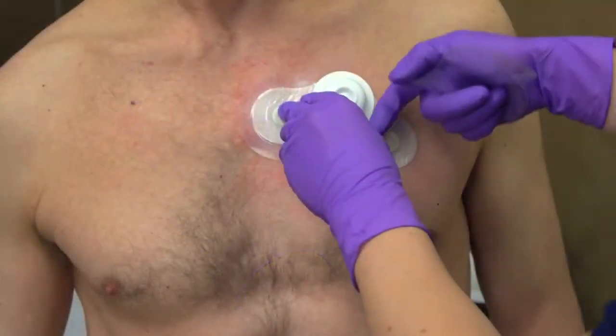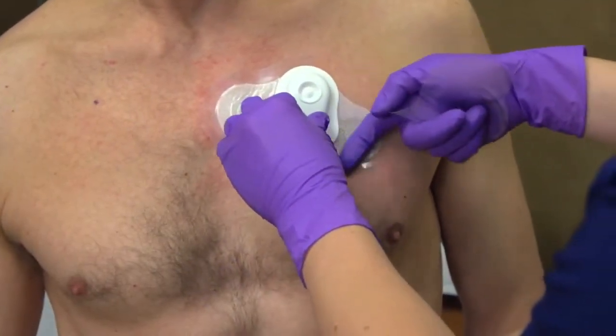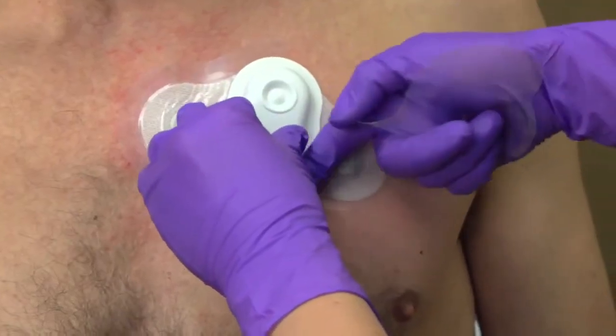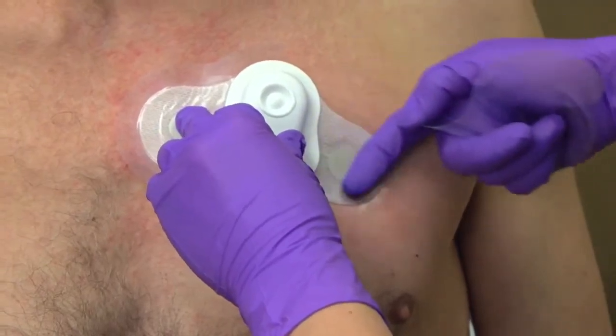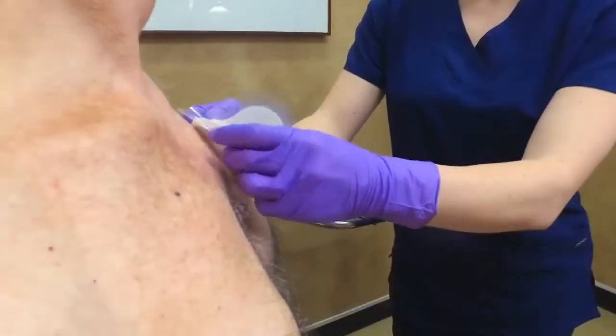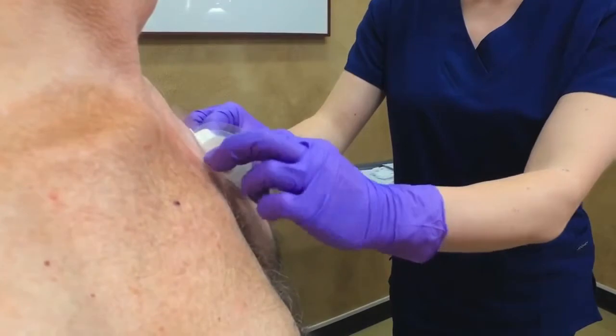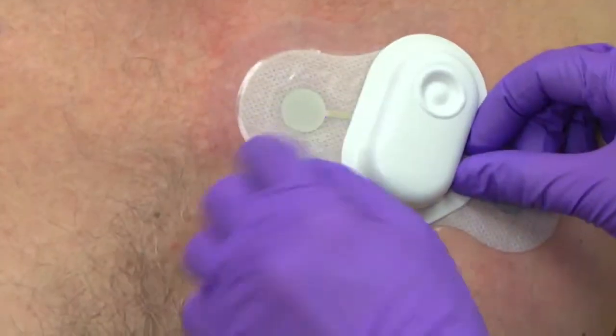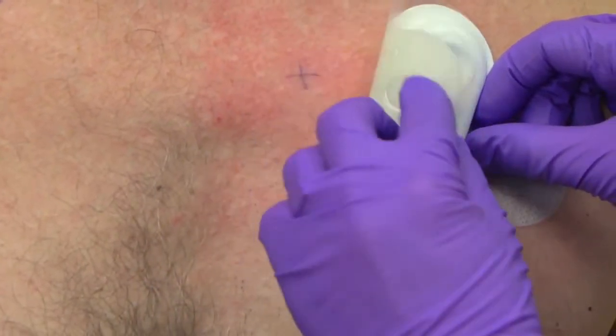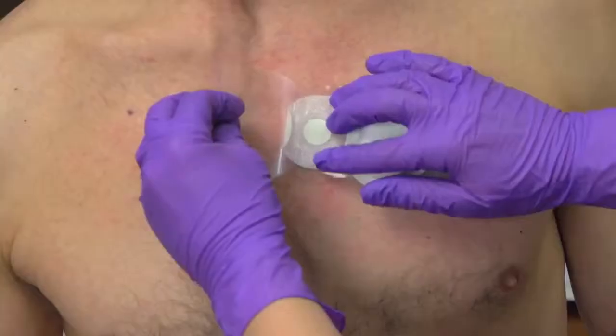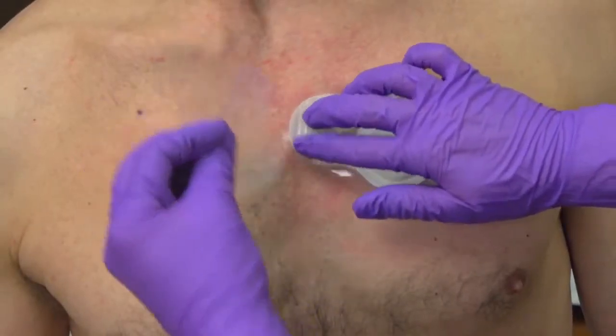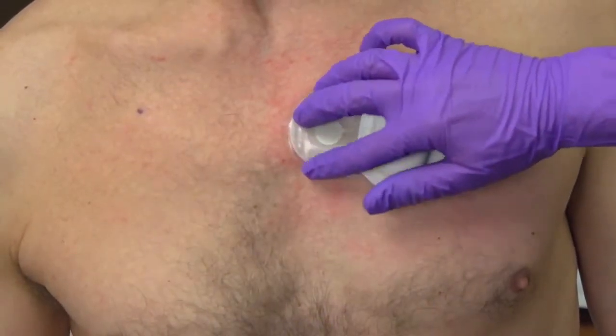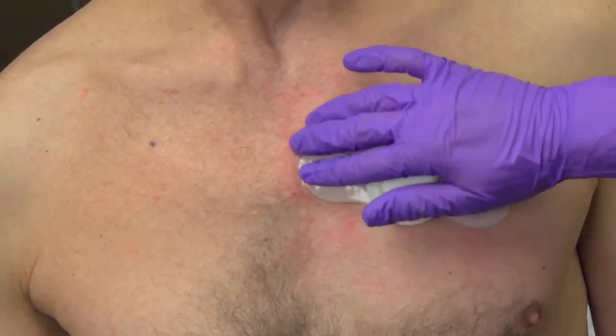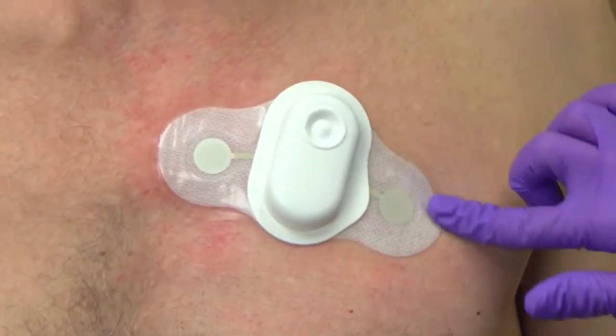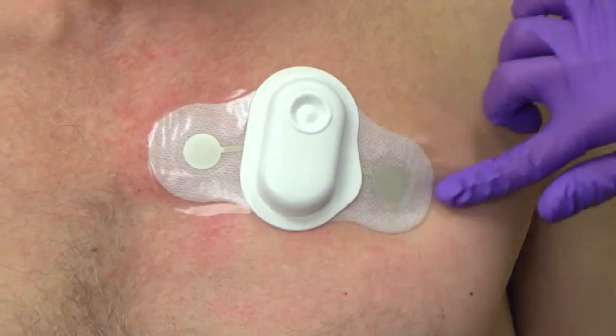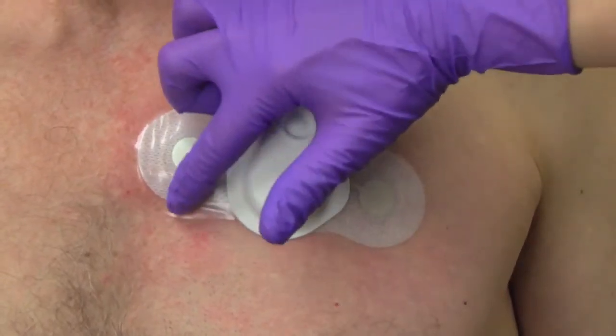Press over and around this side in a firm smoothing motion, taking care not to wrinkle the outer adhesive border. Next, hold and pull to remove the remaining clear flap of the release liner, again matching the gray circle electrode area to the X on the patient's skin. Press around the white sensor cover firmly and smooth out the clear adhesive border against the skin. Lastly, with your index finger, trace around all sensor edges, smoothing as you go.